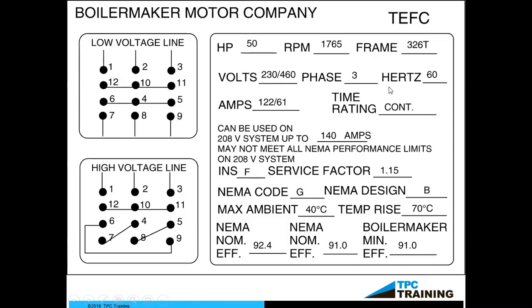It is a three-phase motor, 60 hertz, so made for the USA. Then we can see the FLA, 122 for the lower voltage and 61 amps for the higher voltage. And I want you to remember that a little bit because I'm going to come back to that FLA some. It is a continuous duty motor, so it can run 365 days a year, 24 hours a day, and not all motors are continuous duty, by the way.